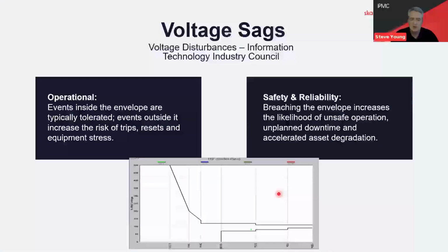So the Information Technology Industry Council produced this curve, and the curve's really useful. It defines the tolerance limits for connected equipment, and it uses duration on one axis and magnitude on the other, just to explain. So generally then, events that are inside the envelope are typically tolerated, they're okay, but events outside of the envelope are going to increase the risk of problems, trips, resets, etc. So if we've got events that are above the curve, then we potentially have an unsafe operation. And below the curve may result in automatic disconnection and increased disruption of the supply. So we need to understand what we can do about that.